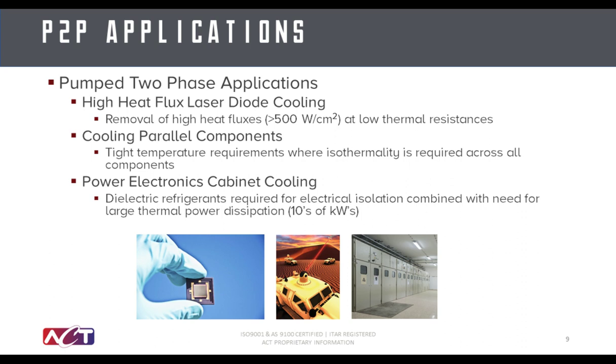Power electronic applications benefit greatly from pumped two-phase systems because they typically require dielectric cooling. If there ever were a case where the refrigerant would egress from the system, it has electrical isolation and wouldn't short out any high voltage components. This provides some additional safety benefits to a lot of power electronics designers.